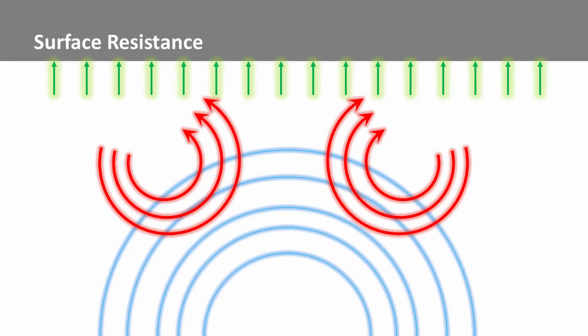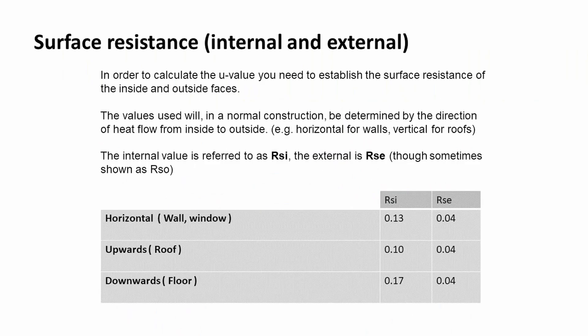We also need to think about surface resistance. Surface resistance can be thought of as a constant value given within the calculation, which relates to the transfer of heat between radiation, convection, and conduction. There are set values for surface resistance within the calculation. If we are looking at horizontal flow for a wall or a window, we have an internal RSI of 0.13 and an external RSE of 0.04, and there are similar values for the other heat flow directions.